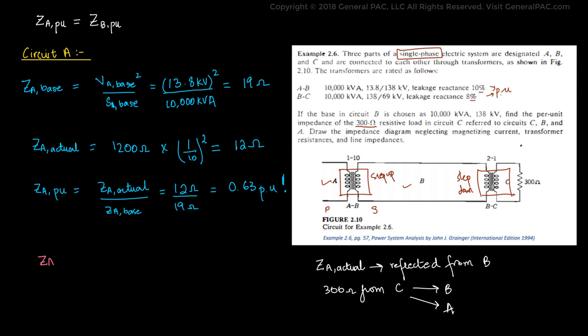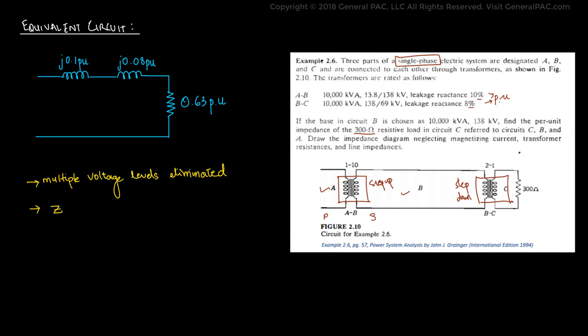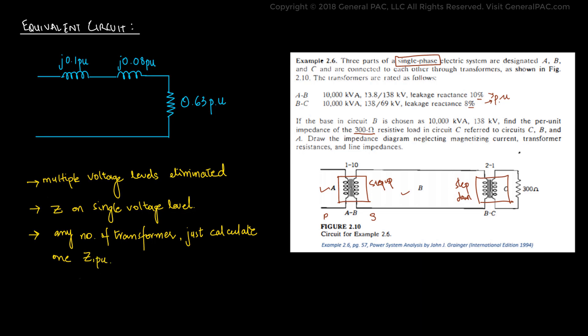Finally, we have the per unit impedance in all parts of the power system, and it equals 0.63 per unit in all parts of the circuit. This reflects that when a power system consists of more than one transformer, the per unit impedance for every side of every transformer remains the same. The equivalent circuit is J0.1 per unit for the first transformer, J0.08 per unit for the second, and 0.63 per unit for the load in circuit C. Multiple voltage levels are eliminated, and the circuit consists of just impedances reduced to a single common scale. No matter how many transformer voltage levels exist, we only need to calculate impedance for one side of one transformer.